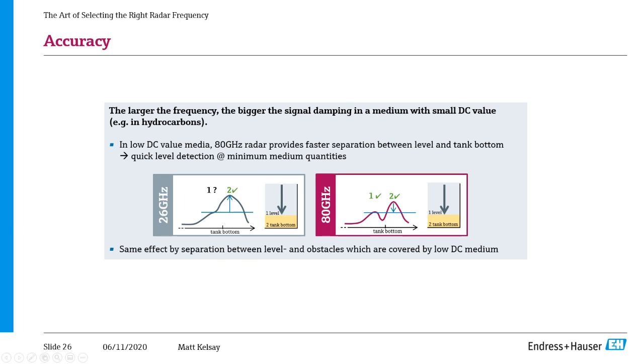The other notable point is measurement in the bottom part of a vessel. Again, with those sharper peaks, it allows us to measure closer to the bottom of the tank. You saw I described at the beginning during the theory how the radar in a low dielectric will actually continue to travel through that media, and you get a reflection off that tank bottom. The left is what you might see with the level close to the tank bottom with a mid or low frequency radar unit. You can see you get a little bit of a hump there on the left where the level might be, but then you get a really big reflection off of the tank bottom, and those two peaks are kind of merged together. There's no way for the radar to distinguish them, so it just locks onto the tank bottom.